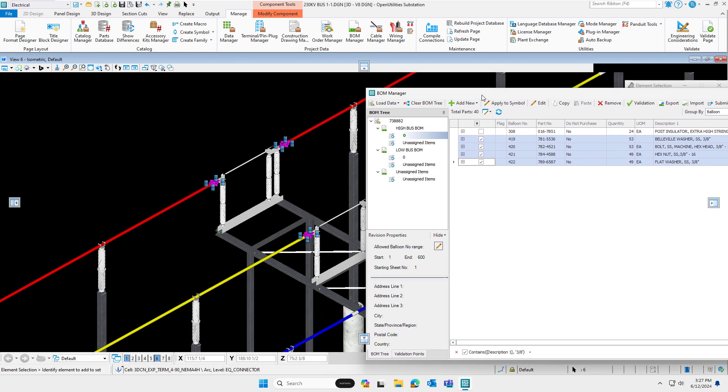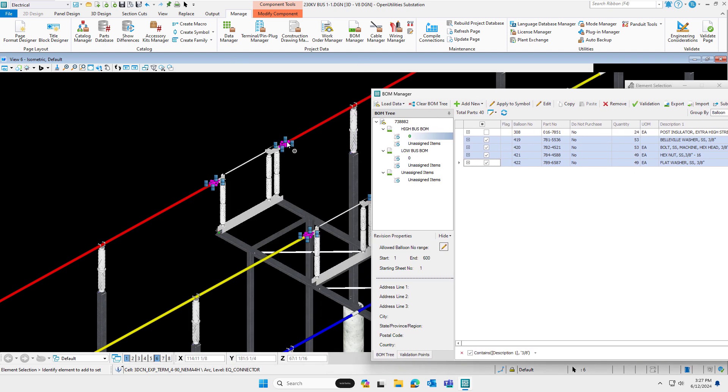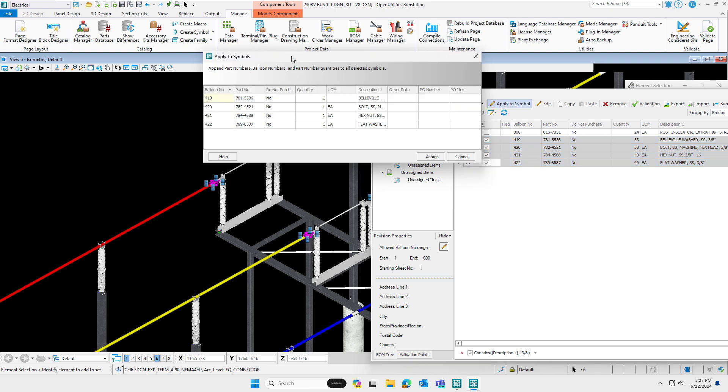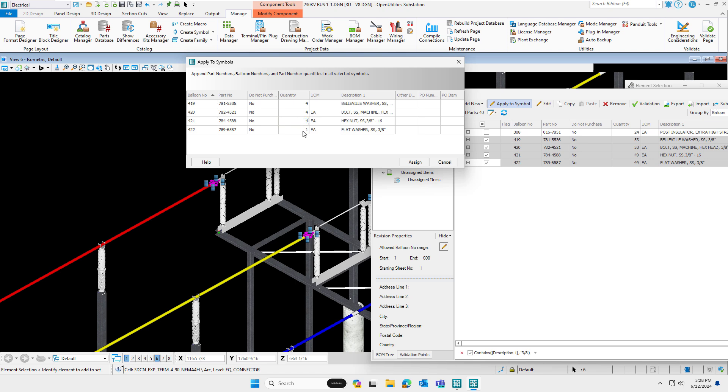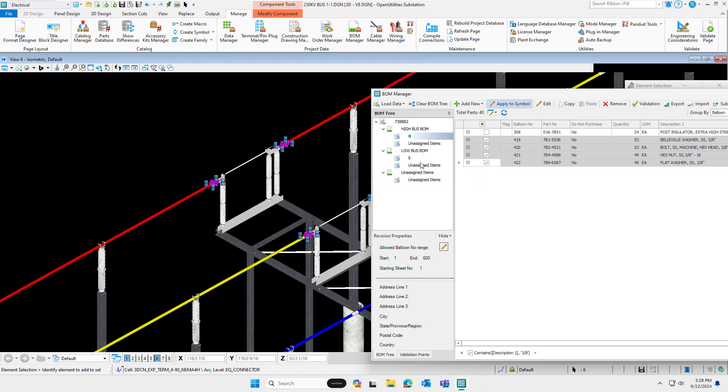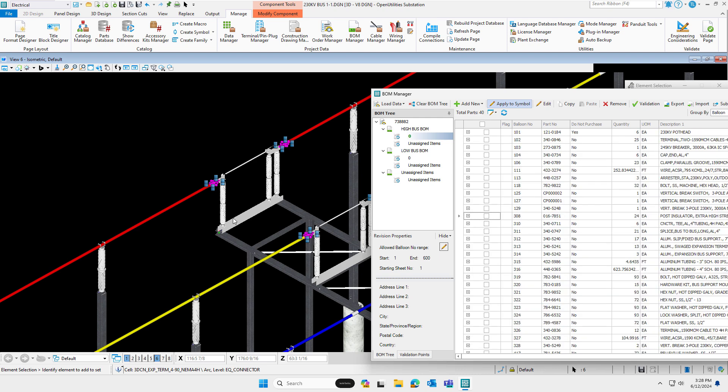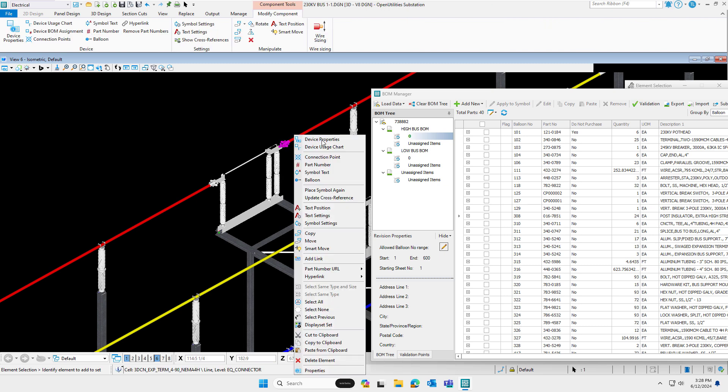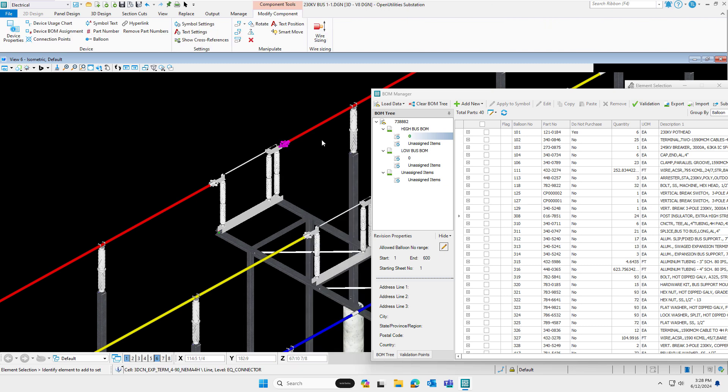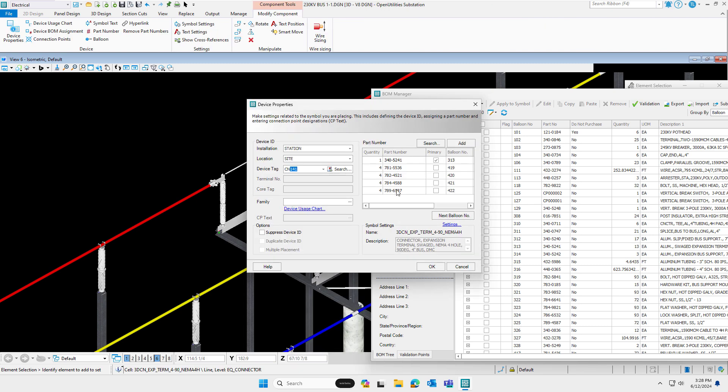And I've identified the Belleville washer. I want this stainless steel bolt. I want this hex nut and flat washer. So these are the part numbers I wish to associate or add them to the existing symbols. I'm going to slide this off to the side. You can see all 6 again are selected, those bus expansion connectors. And now I'm prompted to adjust any quantities as needed. So for example, here you can see the Belleville washer. Maybe I want 4 of those. And I want 4 bolts, 4 nuts, 4 flat washers. Assign. The selected items now have those part numbers. So if I look at the symbols, you will now see that material added as additional parts.